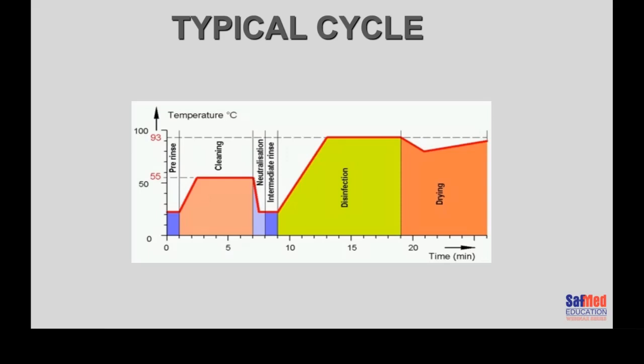You cannot get your instruments by hand when cleaning manually up to 93 or 99 degrees. Firstly, you won't maintain that temperature in a big wide basin, and obviously you can't put your hands in boiling water. And of course, you don't have the value-added benefit of drying. So that's what a typical cycle looks like. There are shorter cycles — you may have a machine that gives you a cycle that's just a disinfection rinse, or you can select a cycle without a pre-rinse.